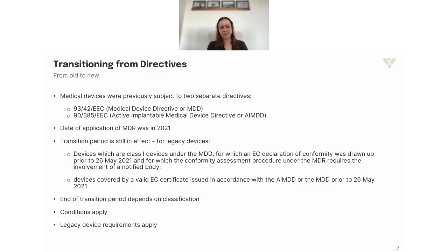So just a little bit of history then, transitioning from the directives, because it wasn't always a regulation. Previously, before we had the MDR, we had 2 separate directives: 93/42/EEC, which was for medical devices, which we often call the MDD for short, and 90/385/EEC, which was for active implantable medical devices, or AIMDD. Now, essentially, the MDR, as we have today, replaces both of those directives.